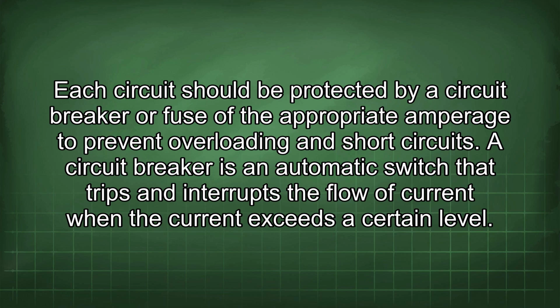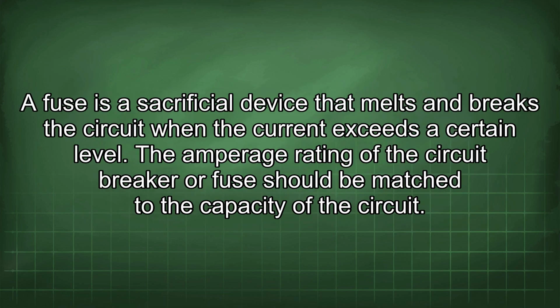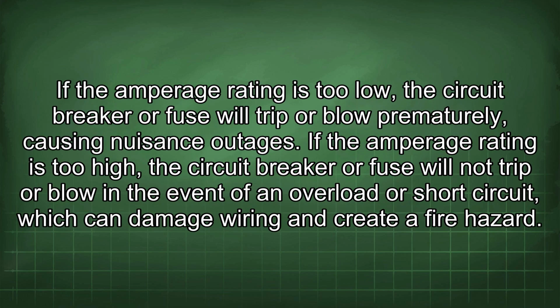circuits. A circuit breaker is an automatic switch that trips and interrupts the flow of current when the current exceeds a certain level. A fuse is a sacrificial device that melts and breaks the circuit when the current exceeds a certain level. The amperage rating of the circuit breaker or fuse should be matched to the capacity of the circuit. If the amperage rating is too low, the circuit breaker or fuse will trip or blow prematurely, causing nuisance outages. If the amperage rating is too high, the circuit breaker or fuse will not trip or blow in the event of an overload or short circuit, which can damage wiring and create a fire hazard.